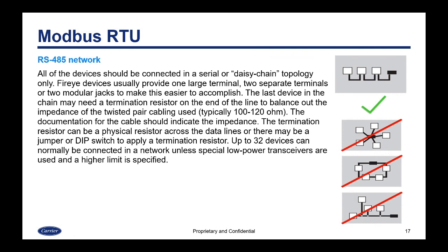Up to 32 devices can normally be connected in a network unless special low-power transceivers are used and a higher limit is specified. According to the normal RS-485 standard, the power requirement allows 32 devices to be connected. Manufacturers of RS-485 transceivers later created lower-power versions, so if you had a quarter-power transceiver, you could have four times more devices.